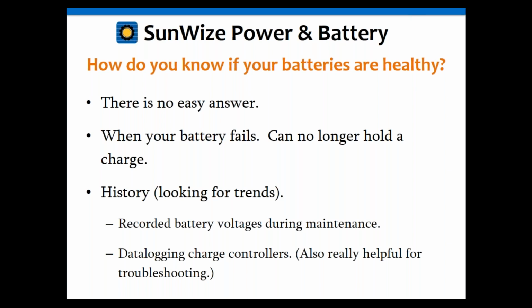Again, one of the things that should be done during standard maintenance is record the voltages and then look at those. If you got a charge controller with data logging, that's another good way to look at it. If you can download that during a maintenance cycle, even if you don't have remote access to it, a lot of our newer ones have remote access via serial ports and Ethernet connections and things like that. But even if you don't have that, a lot of the charge controllers have data storage on board that allows you to plug in with a portable computer and download that data, and then you can analyze it back at the office later.